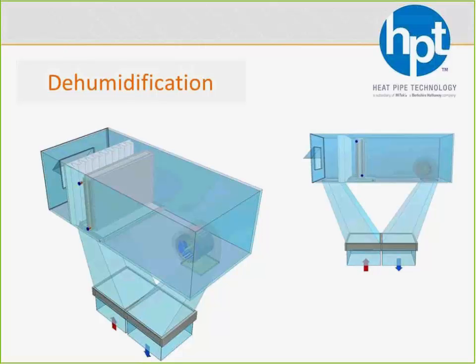So we see this a lot on rooftop units where you've got the return air and the supply air vertically alongside each other. You could actually just run those ducts together and lay the HRM flat, and now we're going to pre-cool the incoming return air and then take that heat and use it as reheat to control humidity. You could also do the same thing in a horizontal duct from a vertical air handler, and set up the natural side-by-side type arrangement.